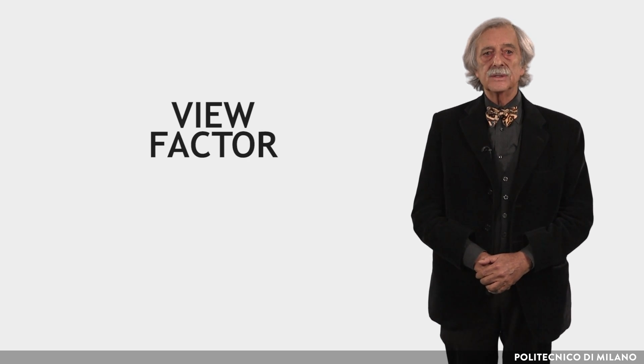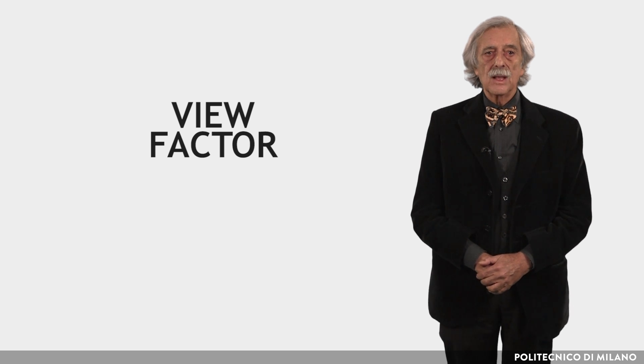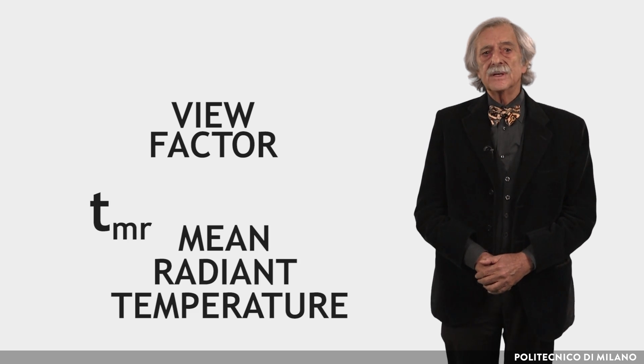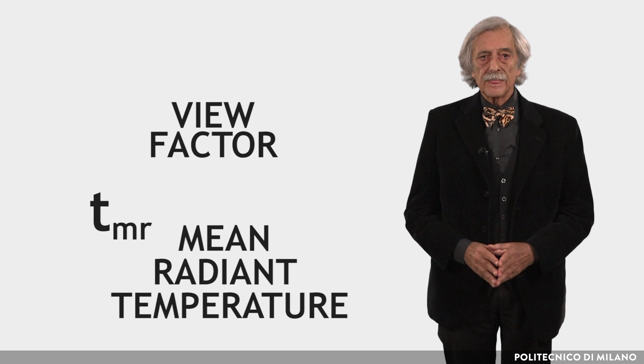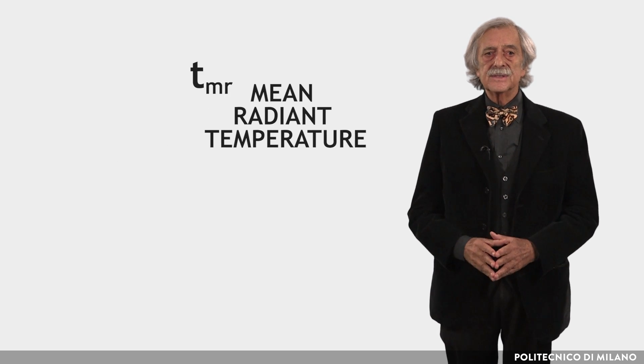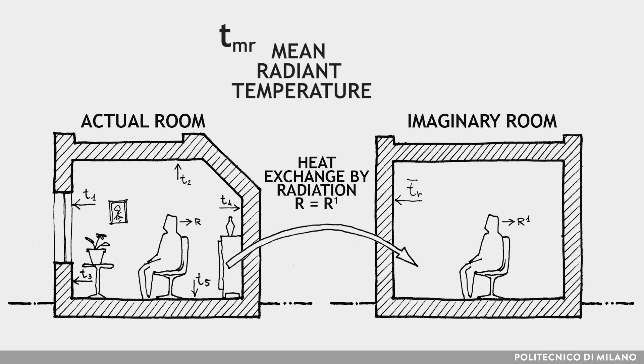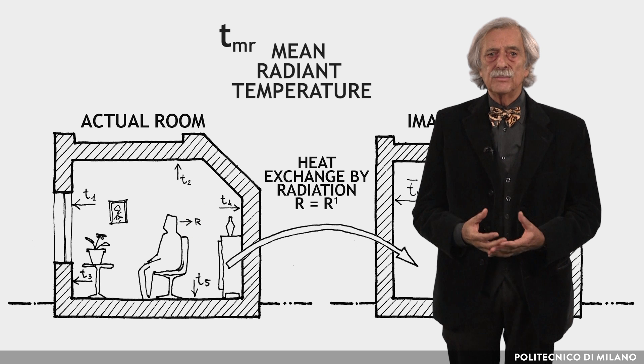Thus, with radiant heat, the apparent size of each radiating surface must be taken into account, not only its temperature. The apparent size is measured with the so-called view factor. In order to take into account this phenomenon in a synthetic way, a specific index — the mean radiant temperature — was introduced. The mean radiant temperature is defined as the uniform temperature of an imaginary enclosure in which the radiant heat transfer from the human body is equal to the radiant heat transfer in the actual non-uniform enclosure.